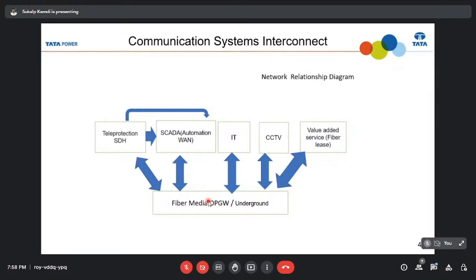Physically, this OPGW conductor is on top of the tower, so obviously no human intervention can go and damage or cut it. Whereas underground fiber is simply dug into the road or footpath, and you know the condition of roads in Mumbai, there are multiple cuts and damages to the fiber. The level of reliability you get with OPGW, over 10 to 15 years, is unmatched, with hardly any degradation in the fiber. This is the beauty of OPGW.